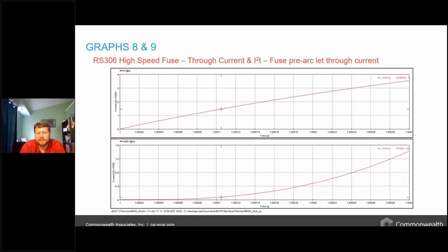So here's what happens: when we have a fault, the fault current doesn't necessarily go from zero fault current to maximum fault current instantaneously. It happens over a period of time. There's a DC rise. So what we have to do is look at the race between these current limiting fuses and the DC rise. Will the fuse burn before the maximum fault current is reached, or will the maximum fault current be reached before the fuse burns?